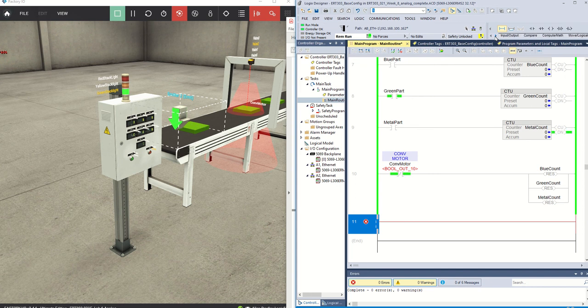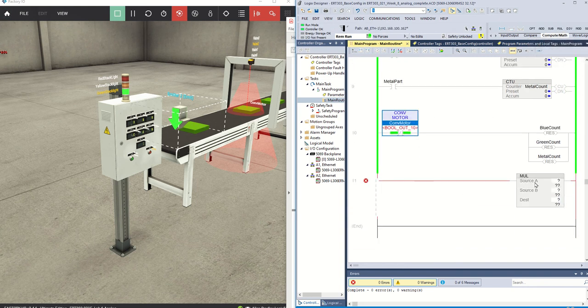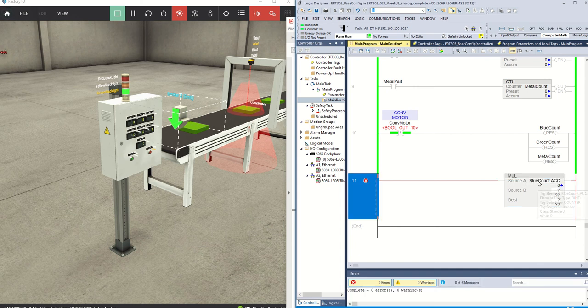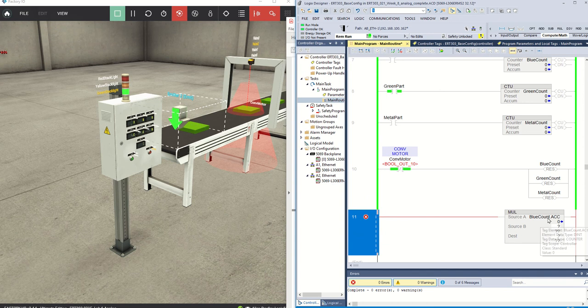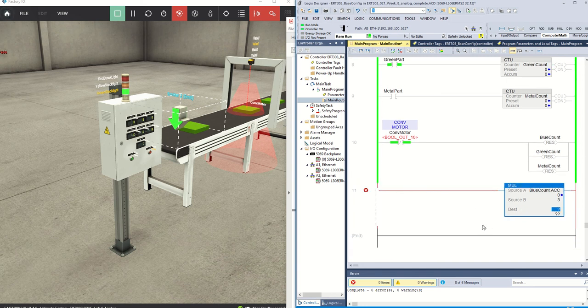Let's go into our instructions and grab a multiply instruction. You'll see we have source A multiplied by source B, which puts the answer in a destination. Source A is going to be 'blue count dot ACC' — the accumulated value of that counter. Source B is just the number 3. The destination will be a new tag called 'blue value'.